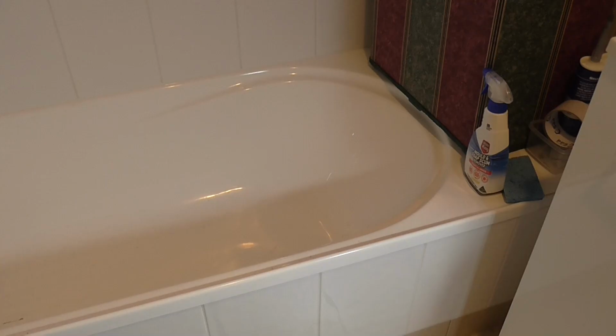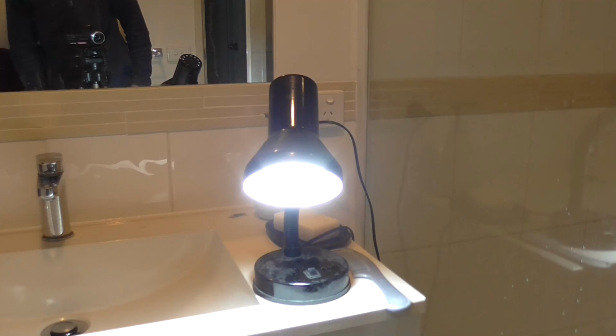So, for instance, someone is taking a bath and they have some electrical device plugged in, like a hairdryer, which is completely stupid, and they accidentally drop it in the bath. Now, there have been several deaths over the years in Australia, especially, from people being electrocuted in the bath for that very reason, for either things falling into the bath that are plugged into an electrical outlet, or they're using electrical devices whilst in the bath. And that is what the RCD is intended for. So let's go look at a physical RCD, and then we'll look at how it actually works.